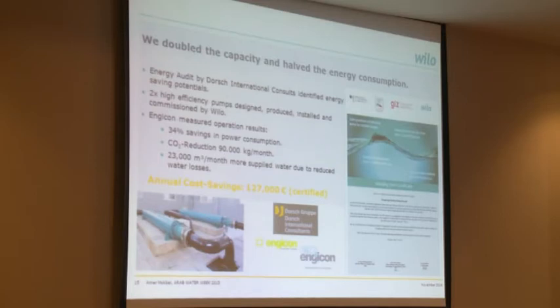The result was 34% saving in power consumption, CO2 reduction of up to 90,000 kilograms per month, and 23,000 cubic meters per month more supplied water, to reduce water losses. Annual cost saving was 127,000 euro per year, and the total cost for the project was around 300,000. That means in 2-3 years, we covered the cost.